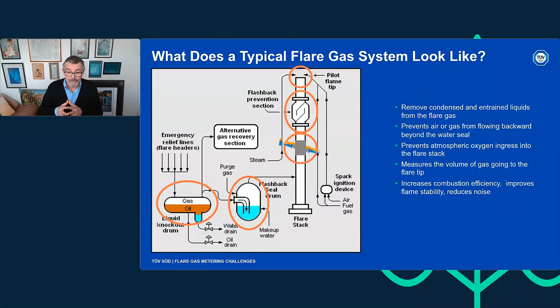But we also have a flare gas meter. In over 90% of cases, if we have a meter, it's an ultrasonic gas flow meter designed specifically for flare gas use. And we also have a flare tip, which is not just a piece of pipe - these are very complex, highly engineered designs. If we want to measure flow rates and combustion efficiencies properly, we need an understanding of these components, the meter and the tip. The tip is primarily there to increase combustion efficiency by improving flame stability, and also to reduce noise - if you've been offshore, in a refinery, or onshore at an exploration site, you'll know these things are very, very noisy.